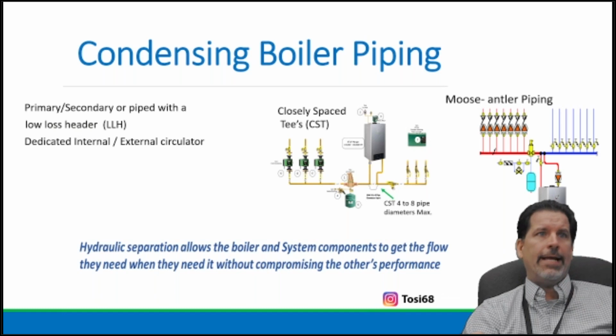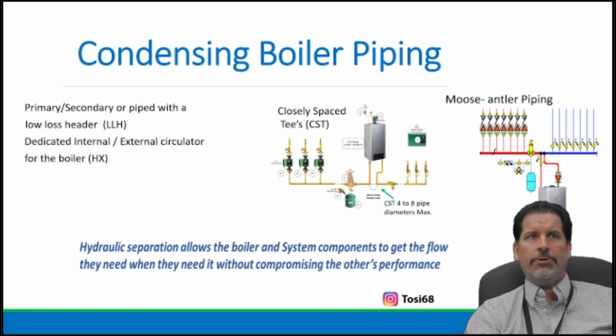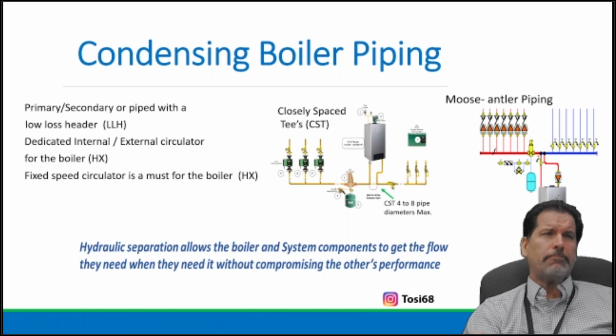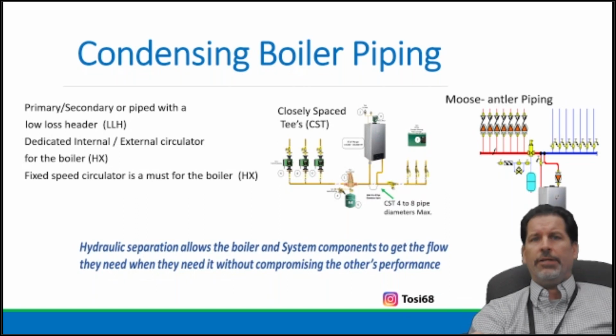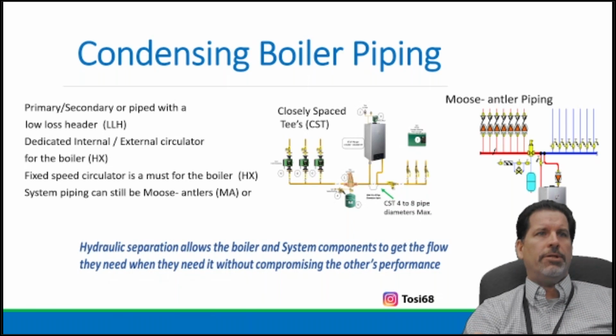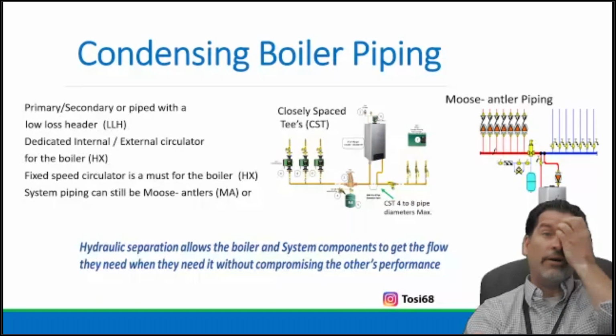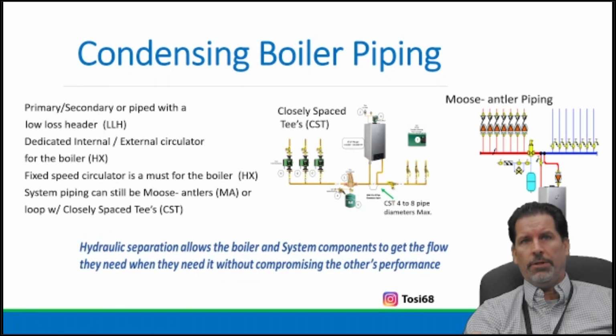We need dedicated circulators, internal and external. This is to make sure that we're flowing the proper GPM across that heat exchanger, right? Not to go off on a high limit. We must have a fixed speed circulator, and that's for the heat exchanger and the boiler. It is guaranteed we are going to deliver a minimum flow based on the manufacturer and the model. System piping can still be the moose antlers, as you see in the upper right corner there, or we can do something with closely spaced tees. You're now building that, right?